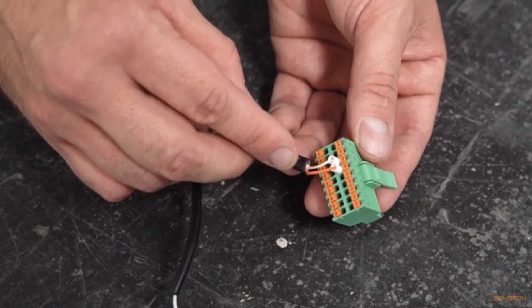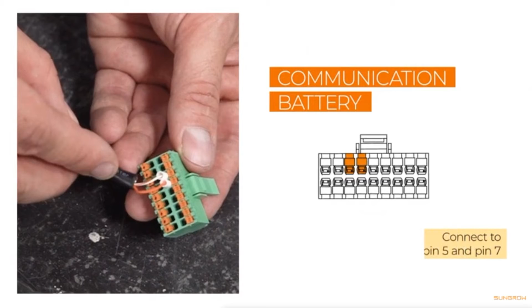In the next step, the battery needs to be connected to the communication plug of the three-phase hybrid. Take the pre-assembled communication plug and connect it to the battery. The other end of the cable needs to be connected to the BMS CAN interface of the communication plug of the three-phase hybrid. Remove approximately 4 to 5 centimeters of the cable sheath of the communication cables. Then, strip approximately 5 to 7 millimeters off the inner cables. Fit the cables with end sleeves before you push them into the plug. Connect the white-orange cable to pin 5 and the orange cable to pin 7.